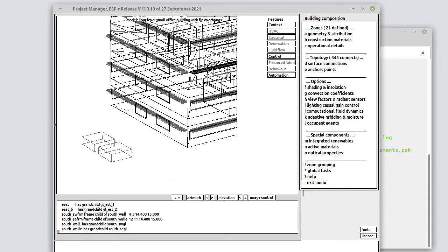To move from imposed infiltration, we would, of course, need to add surface attributes identifying the locations of facade faults. To track flow between rooms and with the ceiling voids, we would need to add doors and air transfer grills. To move from legacy ventilation directives, we would need to add air transfer grills and fans into the ceilings and the mixing box zones.